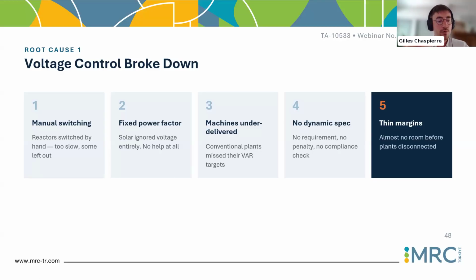And one of the accelerating impacts of this overvoltage was that, yes, when there is overvoltage, some PV plants have an automatic control where they will decrease their active power infeed. Don't ask me why. I think it would be much smarter to play on the reactive power to better control the voltage. But that's a bit the old generation of solar PV, let's say. They decrease their P infeed. But if they are in fixed power factor mode, it means they will also decrease the reactive absorption. And decreasing your reactive absorption in a situation of overvoltage is of course not the good direction, right?